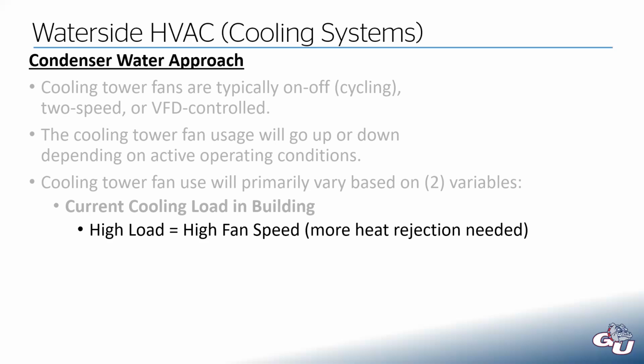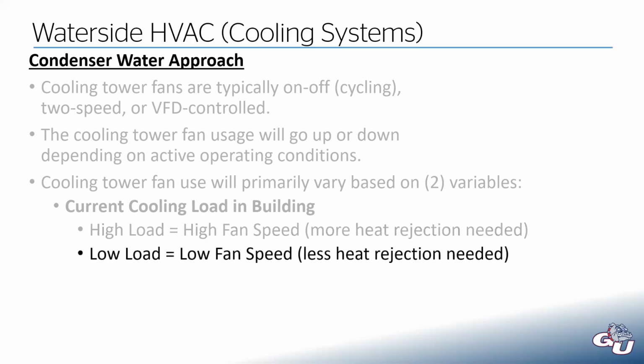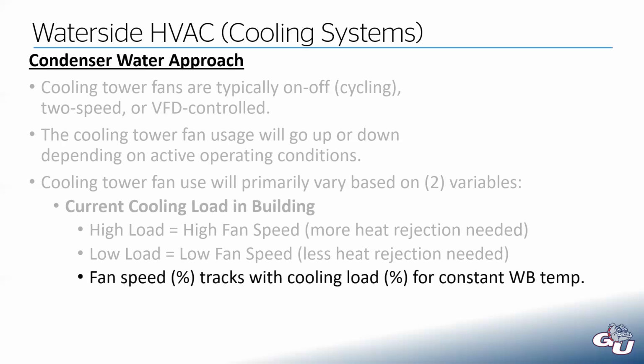Or if it's not VFD controlled, maybe that just means it's going to have a high cycling rate. So it's cycling on 80% of the time, and then it's off 20% of the time. Conversely, if we have a low load, that'll be a low fan speed or a low cycling because we don't need as much heat rejection. The fan speed or cycling is going to approximately track with the cooling load, assuming some constant wet bulb temperature. I'm going to come back to that idea of the wet bulb temperature and the impact that has. But for the same wet bulb temperature, if you have about a 60% load in your building, your fan is probably running at about 60% speed or cycling on 60% of the time.